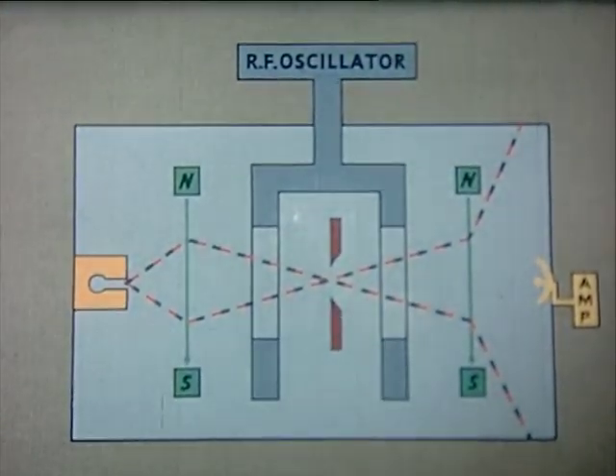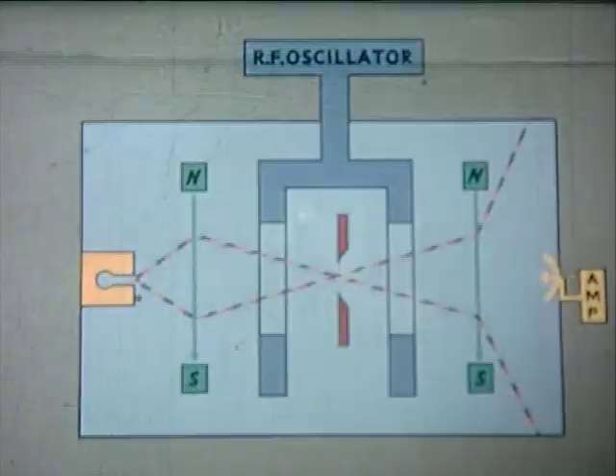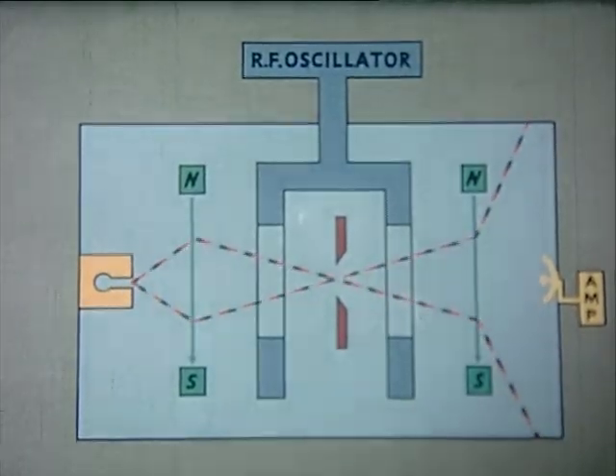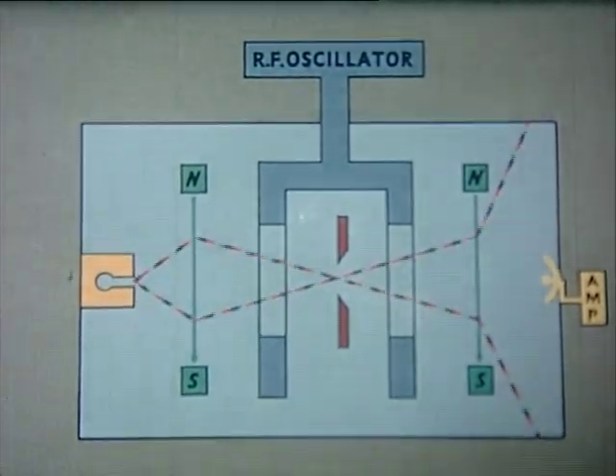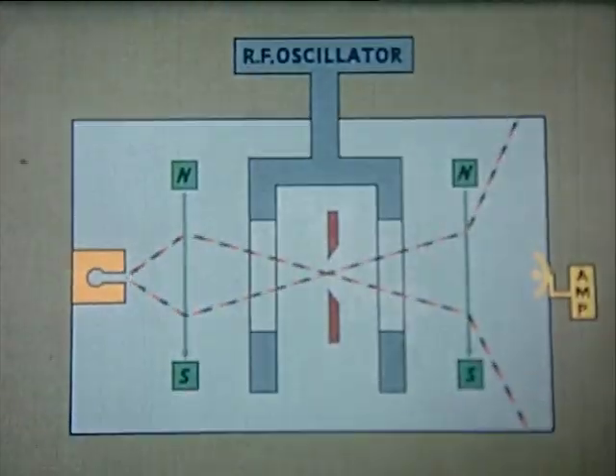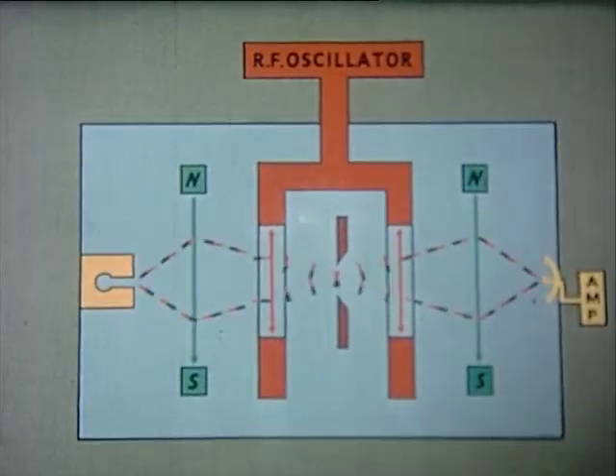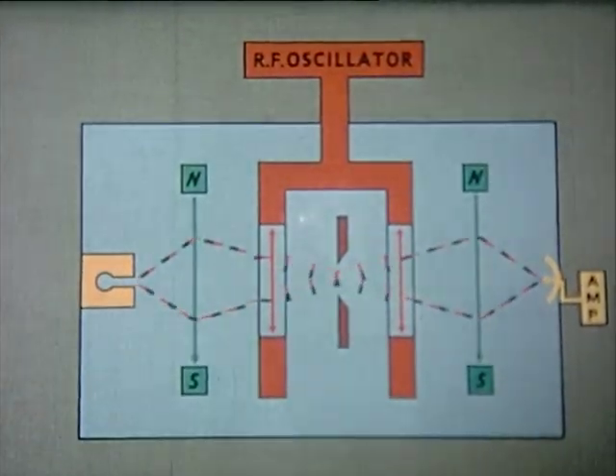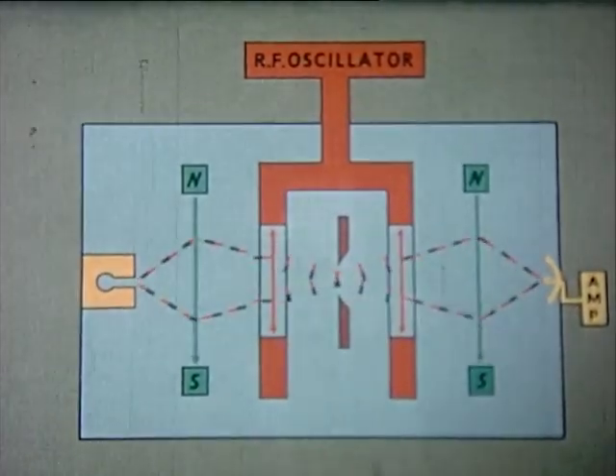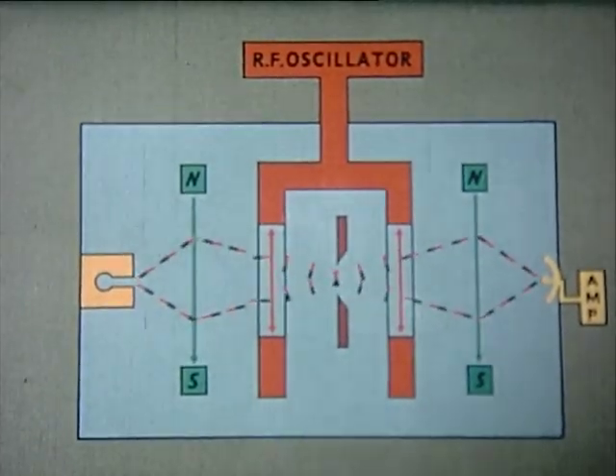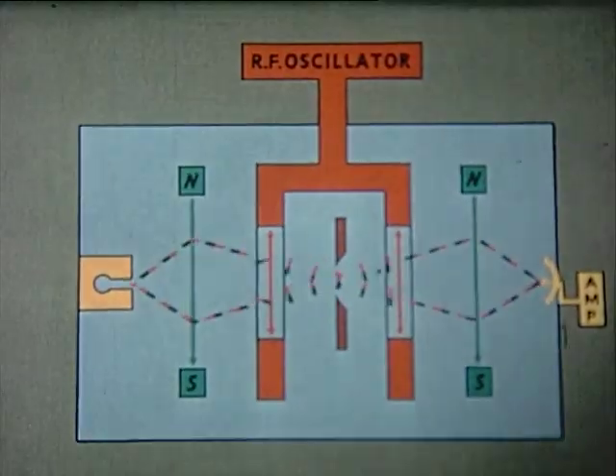Here we see the paths of the atoms without the radio frequency oscillator. No polarity changes occur in the center region and the atoms are deflected away from the detector. When the radio frequency oscillator is applied and when its frequency is exactly equal to the natural frequency of cesium, the atoms respond and reverse their polarity.